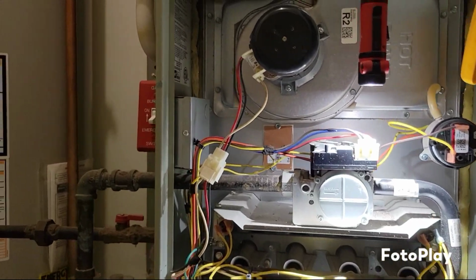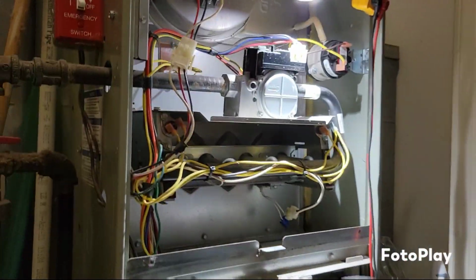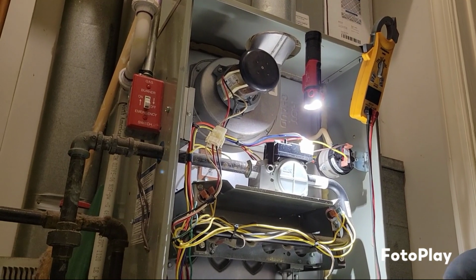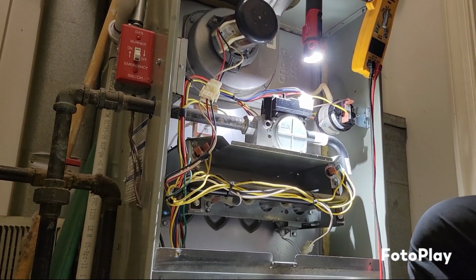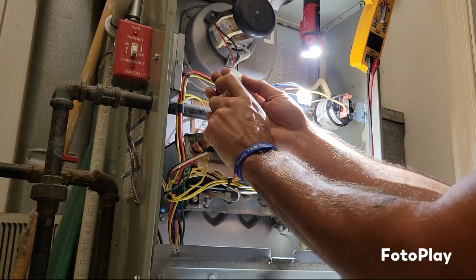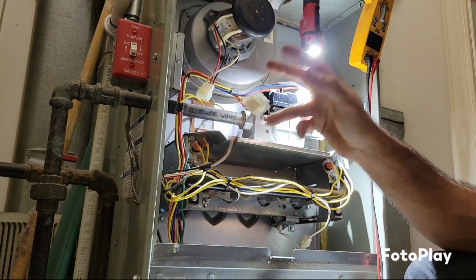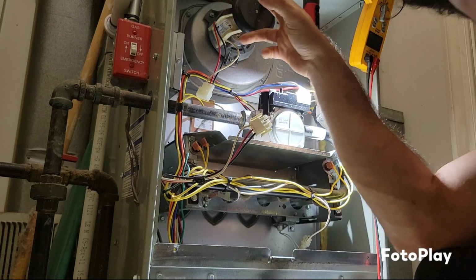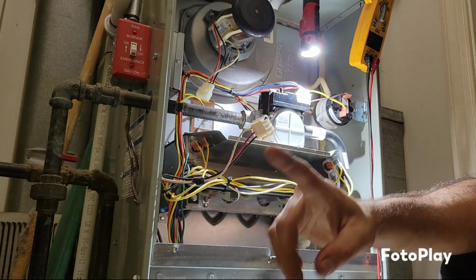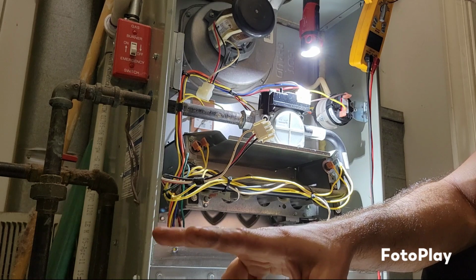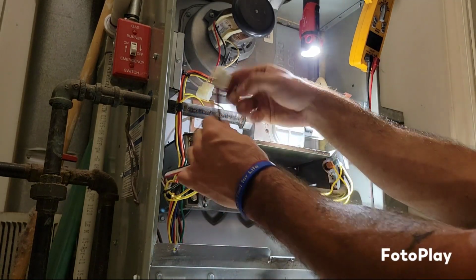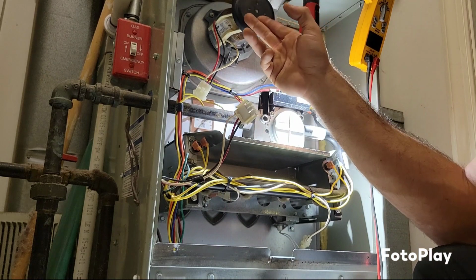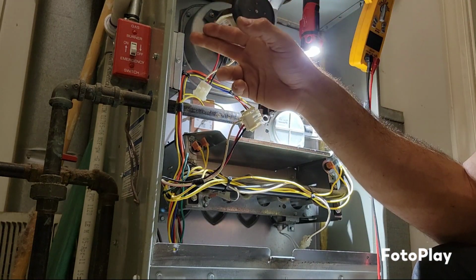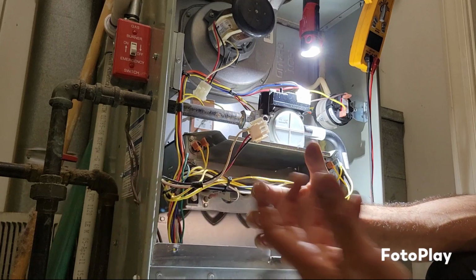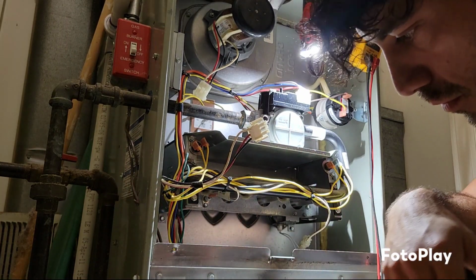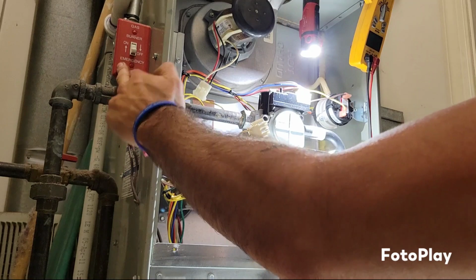So the next thing that we did was basically, see if I can put this right here. Let's see. Yeah. Okay. So there's primarily two things that you can do to check whether a motor is good or bad, right? So number one, we need to establish that we have power, okay? Because if we don't have power going to your motor, then the motor will not spin, right? So obviously we want to make sure we have your line voltage power coming into the unit, which you can check down here. So you'll find the power coming in from the switch.